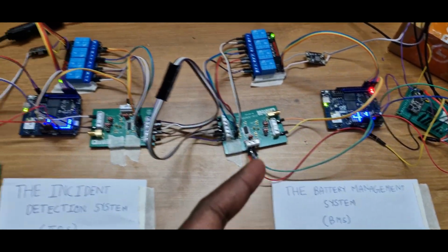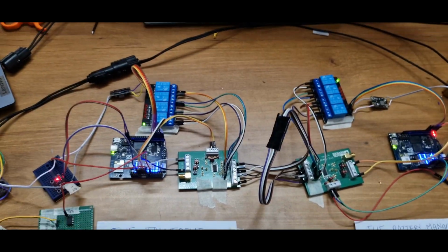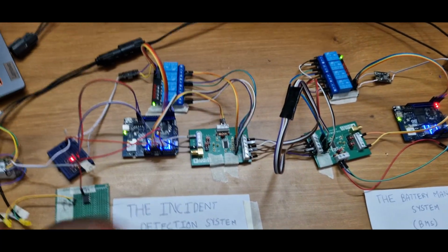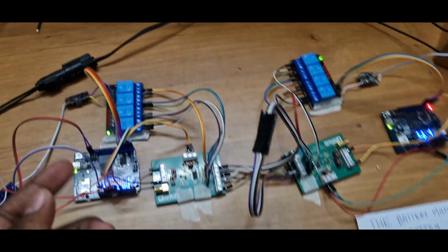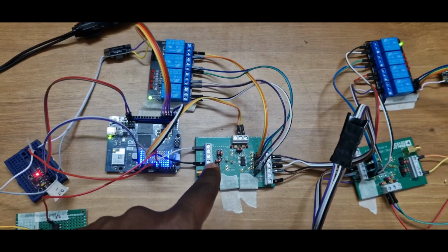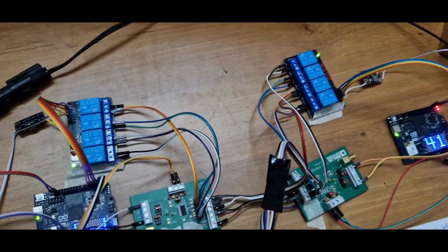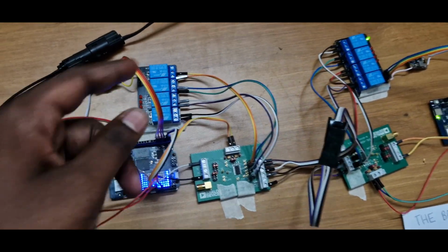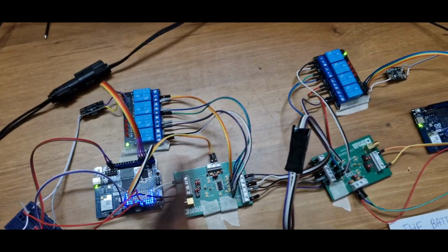If it fails to get the battery information from the BMS, it will wait for 30 seconds. If it still doesn't get anything after 30 seconds, it will do a self-check of the RS485 transceiver by creating a loopback using this relay.